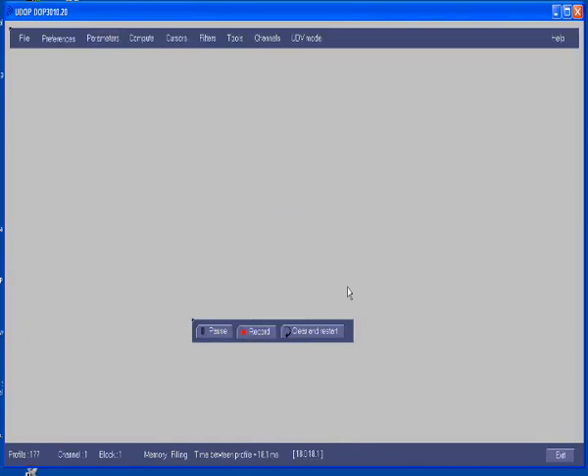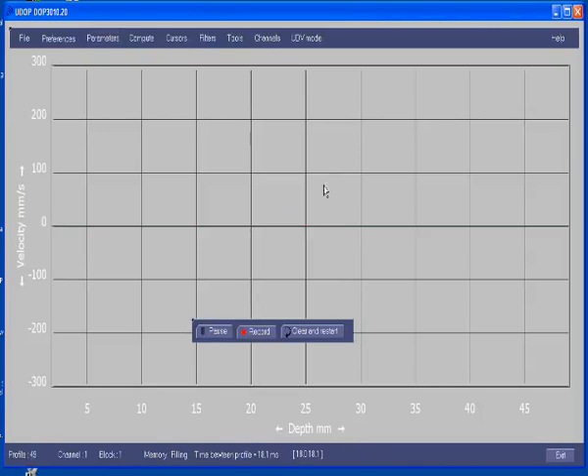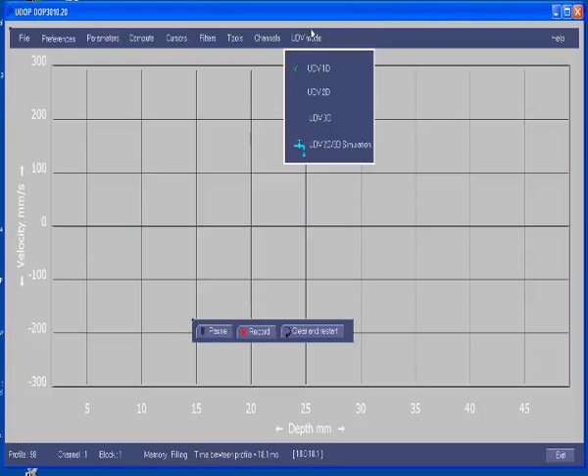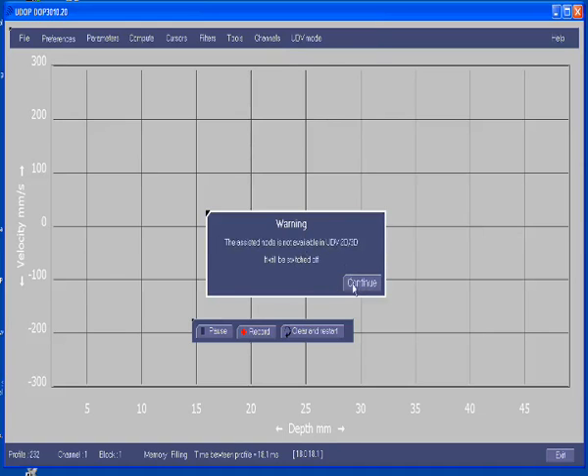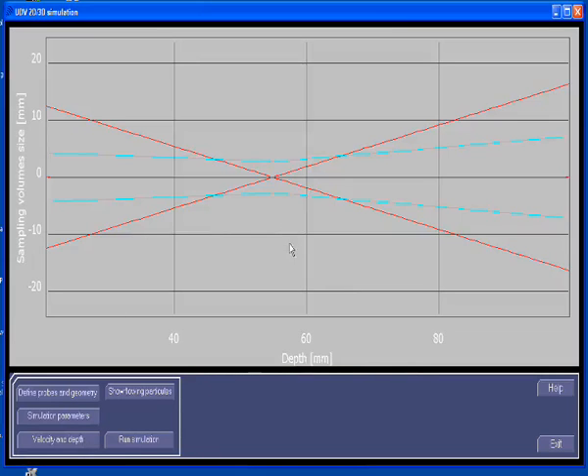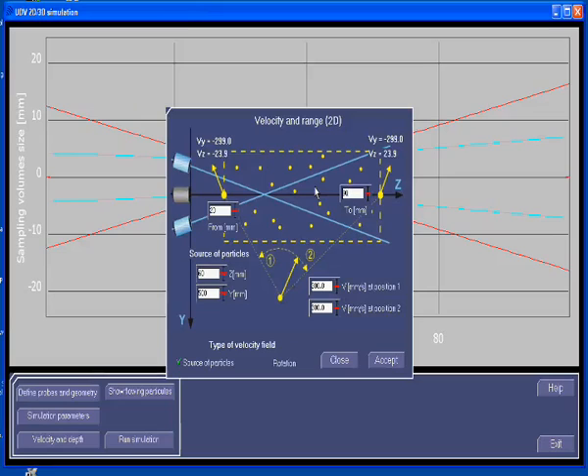Then you will go into the UDV 2D 3D simulation software in order to know how to use the probe, which probe to select and how to arrange the probes. We will define now the velocity field and depth range. We would like to measure from 20 mm up to 90 mm, so enter 90.